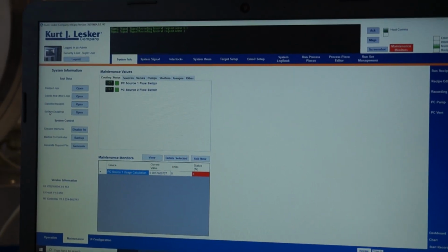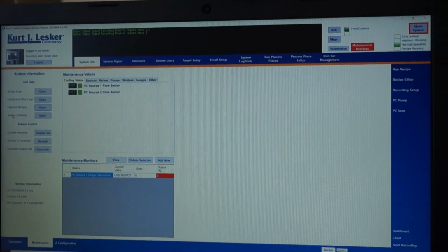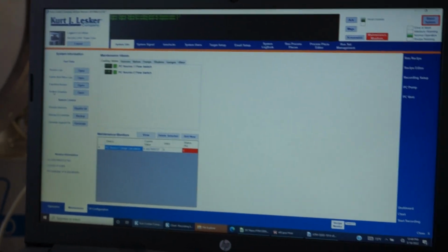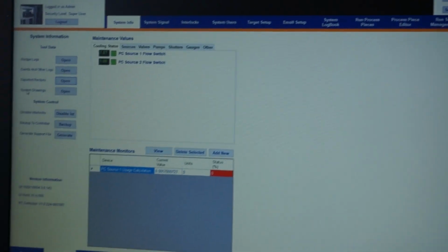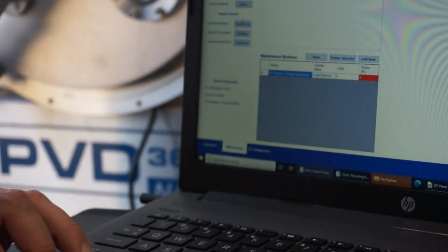And if anything's different than what it's drawn as, we have to redline the drawings. We have to determine where the discrepancy is, and we send it back to engineering. They make a correction, and then we give the final drawings. That doesn't occur by the time the system ships. So if I were to put those drawings in, they'd be drawings that were not correct for the system. But back to where I wanted to kind of get to backup-wise.